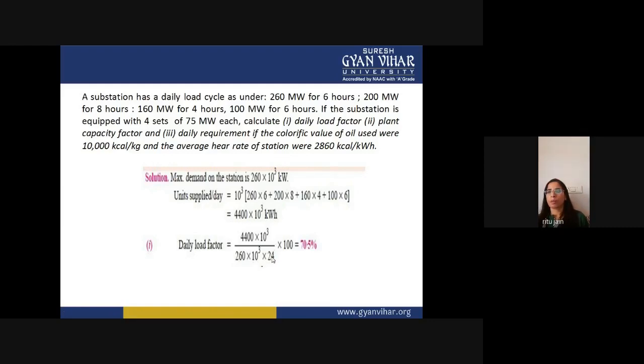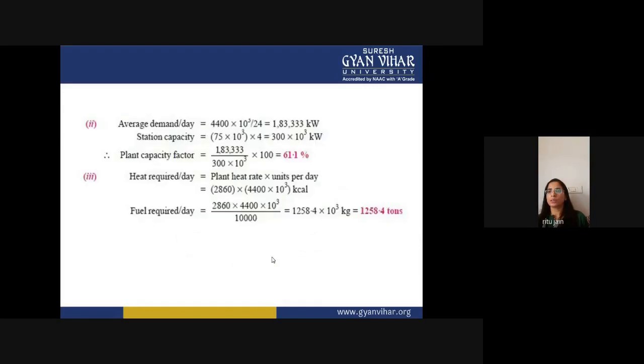Now, plant capacity factor. As you know, the plant capacity factor is equal to average load divided by plant capacity. The plant has four units, so the station capacity is 75 into 10 to the power 3 into 4. And this is your average load, which is in kilowatt. So you divide the average load by the station capacity, and you will get 61.1%, which is the plant capacity factor.